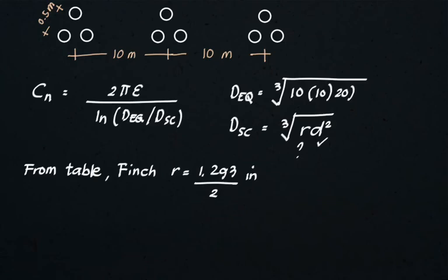But at any rate, if there are conductors which have the same areas, the kcmil, the cross-sectional areas, then the number of stranding and layering will matter. So in this case, we get the Finch outside diameter and then divide by 2 so we can have the R. And also convert it to meter because our conductor spacing between the bundles is in meters, 0.5 meters. So we have to convert that to meter now.